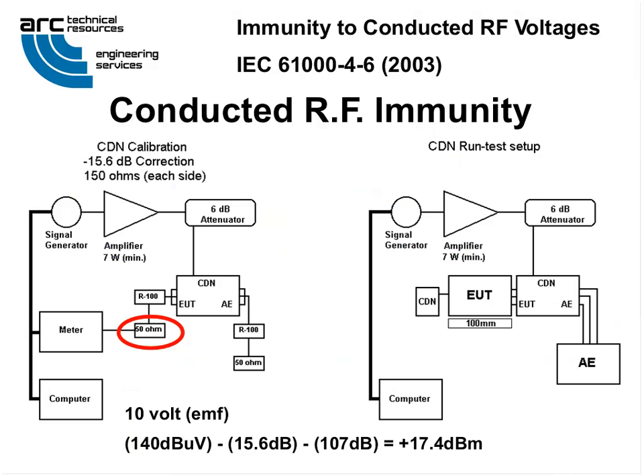Coupling, decoupling level setting procedure is carried out with 100 ohm series resistors, you can see on the left. To each side, we short out all the lines, so it's true common mode. We place a 100 ohm series resistance and a 50 ohm termination to ground. On the left side, that 50 ohm termination is actually the meter's 50 ohm sensor. On the right side, it's a resistive termination. Assuming a 10 volt EMF level, you're looking for 17.4 dBm on the 50 ohm power sensor, which is connected to the power meter shown on the left.